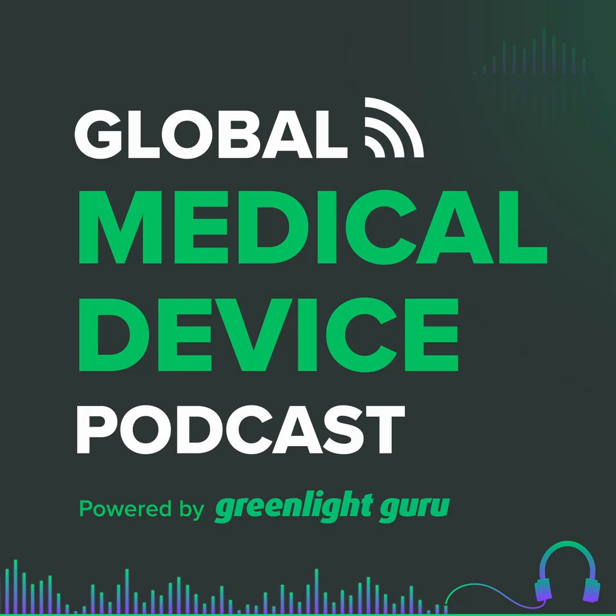But anyway, when I think of some of these tools, dFMEA obviously is one that always comes up in conversation. And like I said, you could go to different communities and see the controversy that arises when people start talking about ISO 14971 and pitting it against all these specific tools such as dFMEA. When I think about dFMEA, we talked about engineers and their preference for convergent thinking. I see dFMEA as a bottom-up, product-focused approach to risk management. I want to see if you agree and see what your thoughts are, or if you want to expound any on that. Yeah, I completely agree.